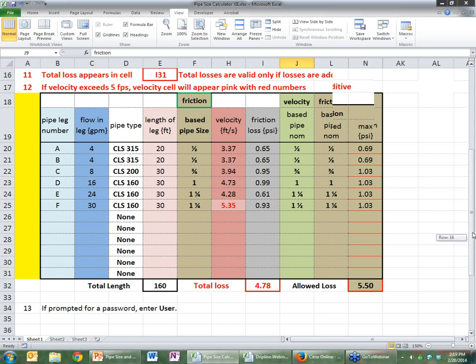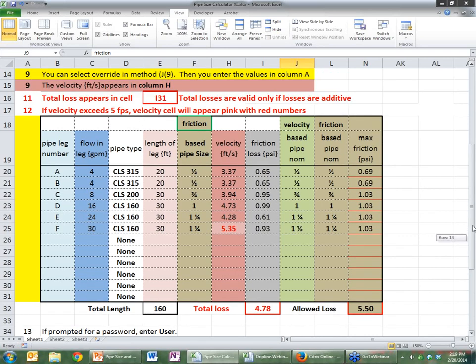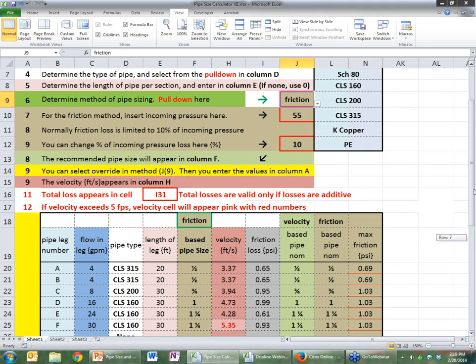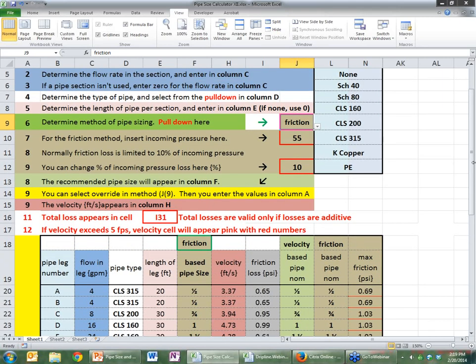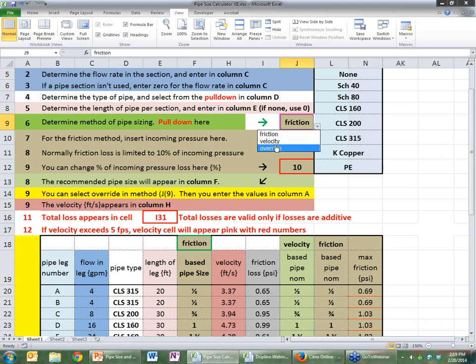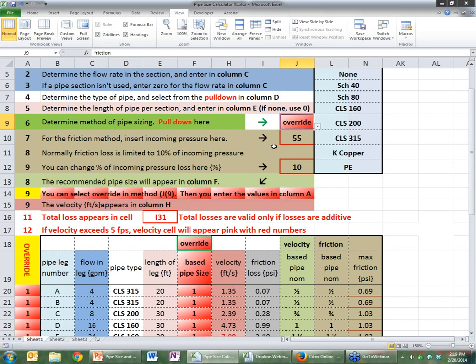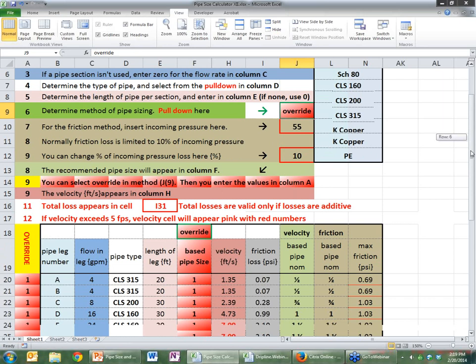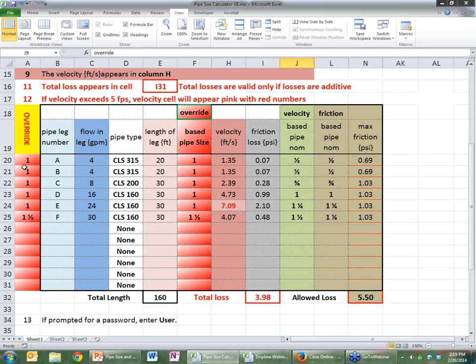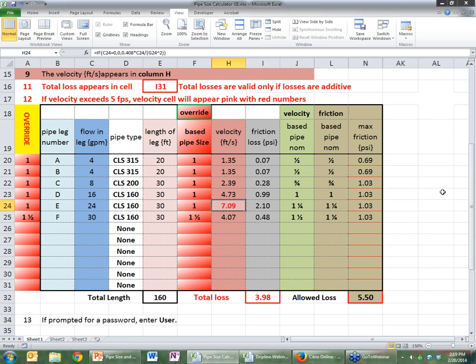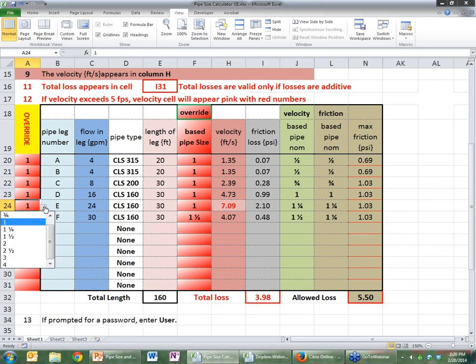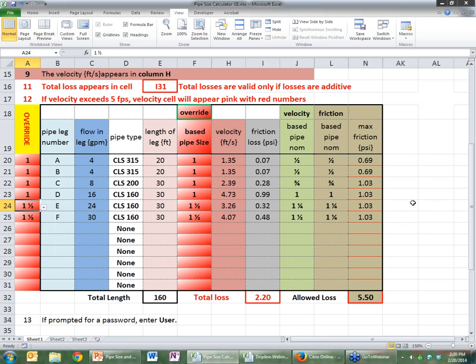And I've shown you earlier, if we switch to velocity, then this pipe size goes to the inch and a half, as it shows right there. Now, let's say that you're in a situation where you don't want to stock or carry in your truck or whatever, all those different pipe sizes, and that you want to say, okay, I'm only, for example, I'm only going to use one inch and inch and a half. I'm not going to use those other sizes. So we can go to override. Notice in override, everything turns red here. And I've set this up ahead of time that these are all one inch over here, which then transfers to this column. That's the override size, except for section F, which is inch and a half. Now, incidentally, you see, well, that velocity is pretty high. You probably don't want to put, that probably shouldn't be allowed. So let's change it to inch and a half and you'll see the velocity comes down within limits.